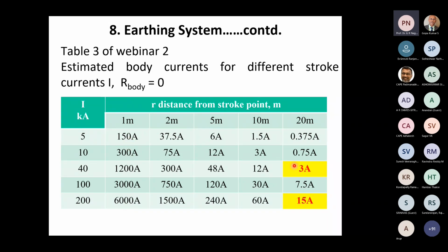Now, supposing you think of the hemisphere of radius 20 meters, as we have seen in our present example, the body current can be 0.375 amperes for 5 kiloamperes, 3 amperes for 40 kiloamperes, and 15 amperes for 200 kiloamperes. So we'll see that these things become very safe if the equivalent radius of the ring conductor is about 20 meters. Now this example will greatly highlight the importance of having a ring conductor all around the building, which bonds all the bottoms of the down conductors. I will repeat it. All the bottoms of the down conductors are bonded by this ring conductor.